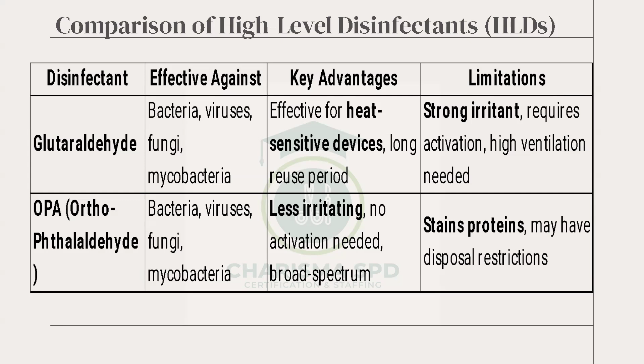As I said, the glutaraldehyde is most often found inside other formulations. For example, alcohol. When you go to the field, you see these kind of things. Strong irritant, requires activation and high ventilation. Ventilation is needed for all of them. As I said, you need a very good level of ventilation, and the ventilation is 10 air exchanges per hour. Remember we talked about that. 10 air exchanges per hour. Okay. Next slide, please.